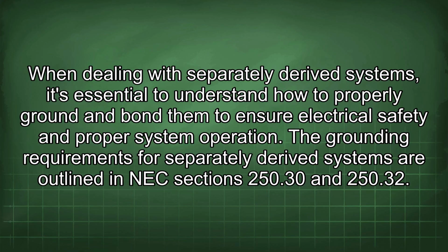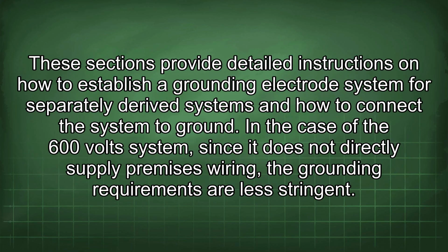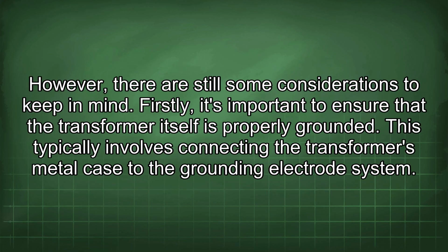The grounding requirements for separately derived systems are outlined in NEC sections 250.30 and 250.32. These sections provide detailed instructions on how to establish a grounding electrode system for separately derived systems and how to connect the system to ground. In the case of the 600-volt system, since it does not directly supply premises wiring, the grounding requirements are less stringent. However, there are still some considerations to keep in mind.